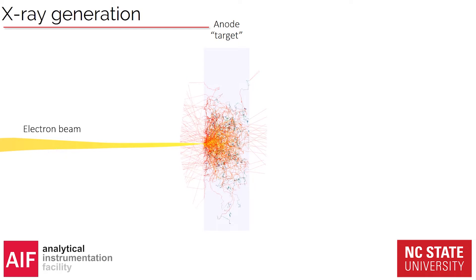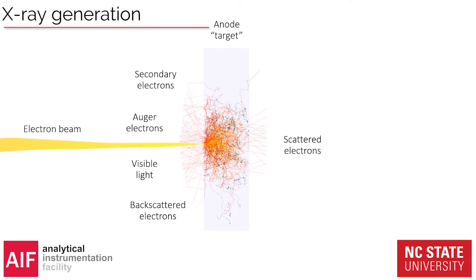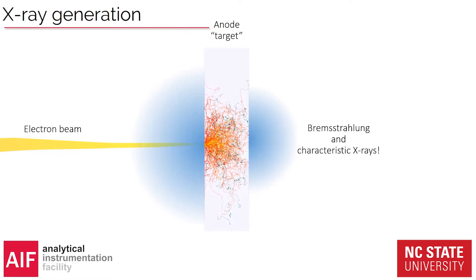What we do with the electrons is fire them into an anode or target material where we get a lot of interactions. You will generate secondary electrons, Auger electrons, visible light, backscattered electrons, scattered electrons — a lot of stuff. But most importantly, you will generate X-rays: Bremsstrahlung and characteristic X-rays. Not a lot of them actually — it turns out only about one percent of the energy put in will actually be generated into X-rays, and an even smaller amount will go in the direction we want. So there is a very big loss in this step.